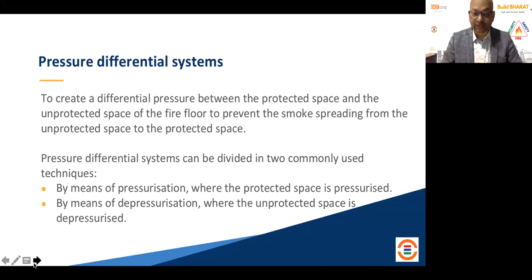So this is how you need to see where you need to create pressurization, where you need to create depressurization. Wherever depressurization happens, that means you are going to switch on the exhaust, and smoke is going to go out. Pressurize means you are going to create positive pressure in the adjoining area, and that's how you are going to create pressurization in that area which is protected.